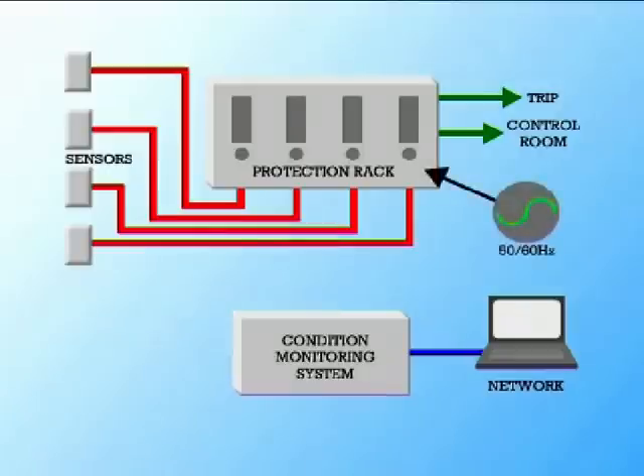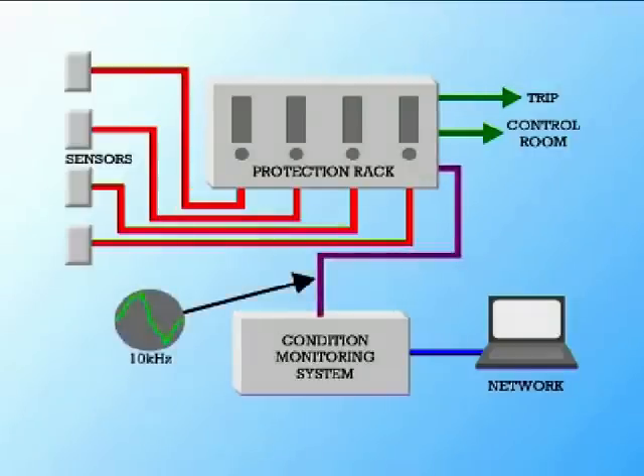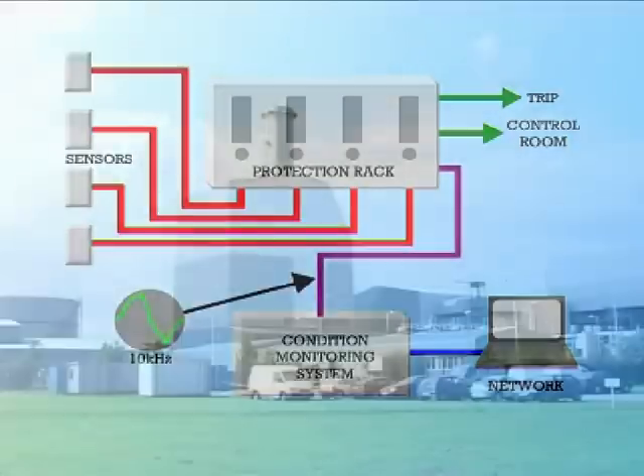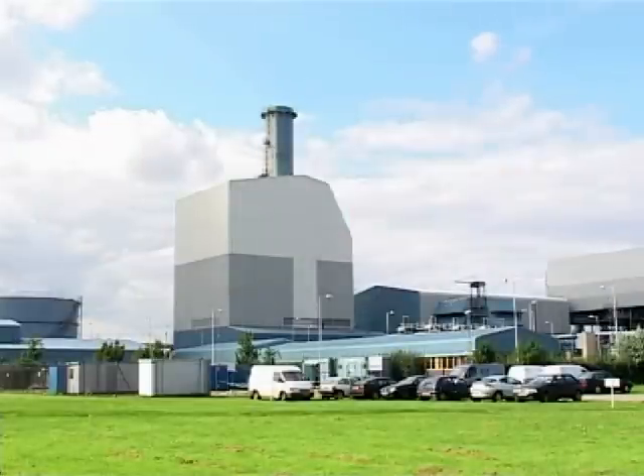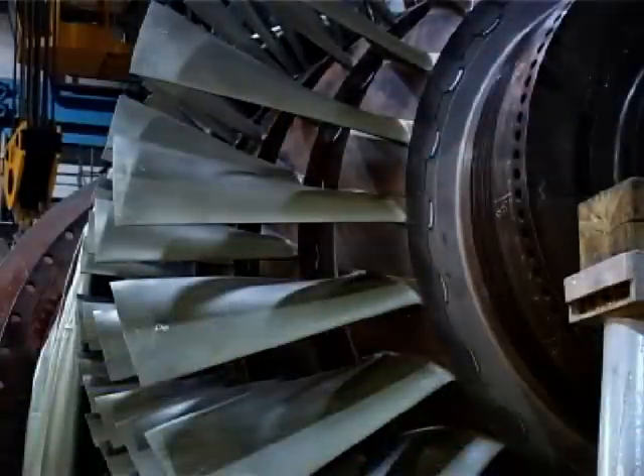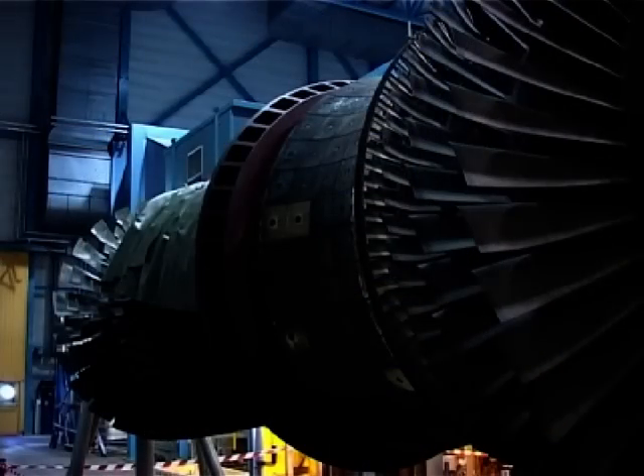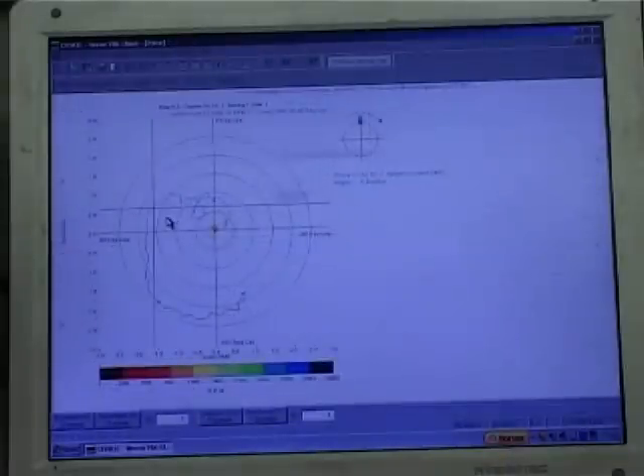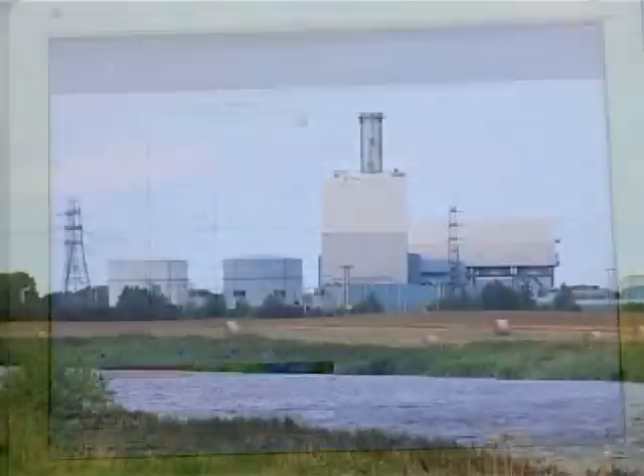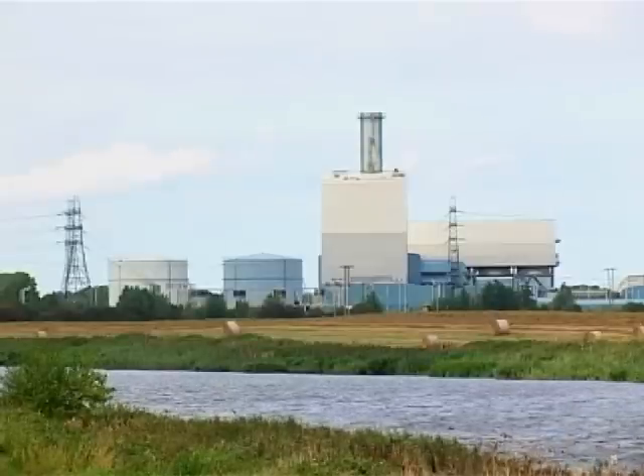So the historic single frequency sensor calibration at 50 or 60 Hz will only test a fraction of the range over which the transducer is now being used. Having made a large investment in condition monitoring equipment, it makes sense to ensure that the benefits of this investment are not jeopardized by faulty transducers. This is becoming increasingly important as condition monitoring is used to extend the periods between maintenance and to help maintenance personnel pinpoint the cause of change in vibration.